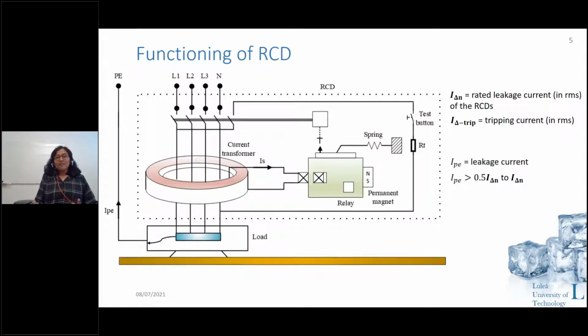So what is an RCD and how does it function, how can these waveform distortions affect an RCD, and where do these waveform distortions come from? These are quite a lot of questions, but first let's start with how it functions. An RCD is a simple device which has mainly two parts. One is a summing current transformer, which is here, and the other one is an electromechanical relay with a permanent magnet. Under normal conditions, when the three-phase current returns through the neutral, the summation of the current is equal to 0. Hence, there is no magnetic field present, and the current in the secondary coil, IS, is equal to 0. So the RCD doesn't do anything.